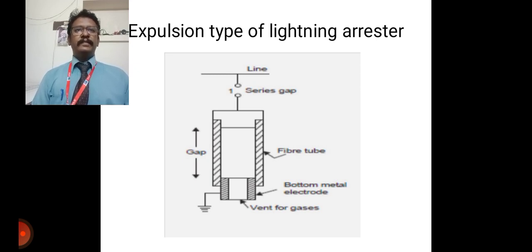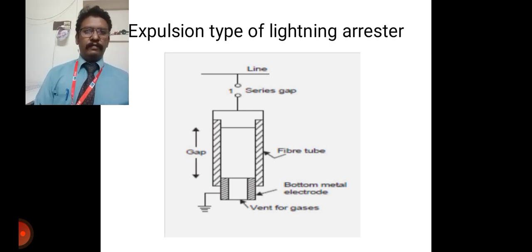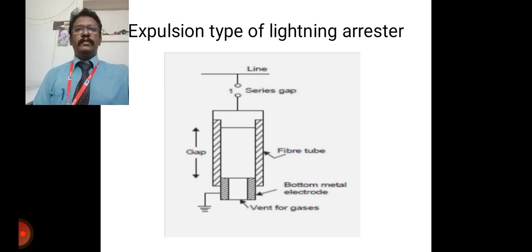Next, you have spark gaps. Then inside the tube you have an open vent at the lower end for the gases to be expelled. At the bottom you have that provision to expel those gases. It is desired that the breakdown voltage of that particular tube must be lower than the insulation for which it is to be used. You can see here this kind of expulsion type nowadays has completely replaced the rod gap.